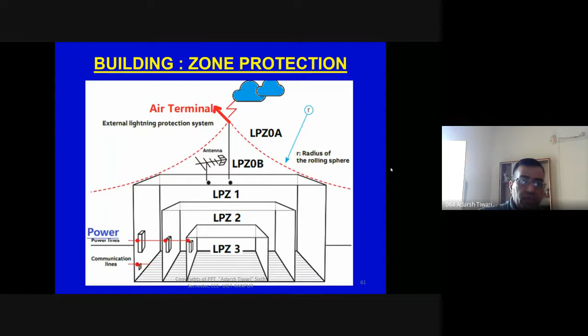Every zone has a different class of protection. Like power, SPD of power line is 690 volt. SPD again of a different zone of power line is 230 volt. So zone 0 is outside, zone 2 is inside, and zone 1 is in between. Whenever we design any electronic or electrical equipment, first we have to see what the zones are and what type of SPD is required at that particular zone.